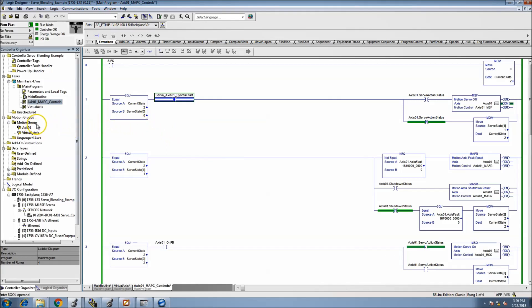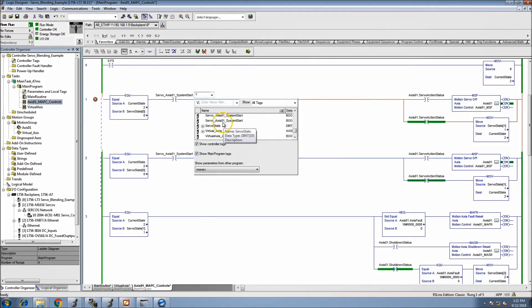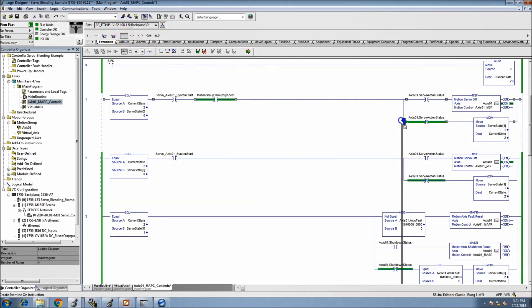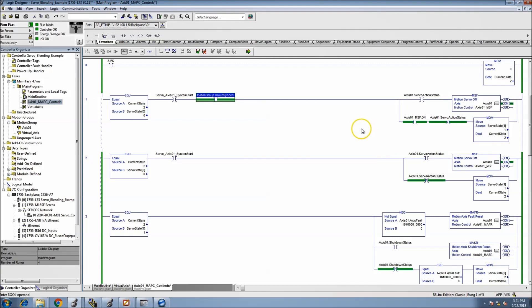First and foremost, we need to monitor the motion group. Our motion group is called 'motion group,' so we need to come in here and use the tag for the motion group to make sure the group is synced. This verifies that the group is healthy and the servo controls are able to be utilized without faulting out. I also like to verify that the instruction actually happened by using the done bit.